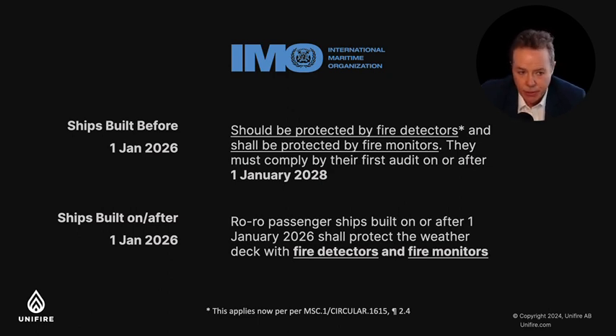But the new SOLAS regulations do require that they be protected by fire monitors, and they must be in compliance by January 1st, 2028. So for all new build ships starting January 1st, 2026, they shall be protected both by fire detectors and fire monitors.